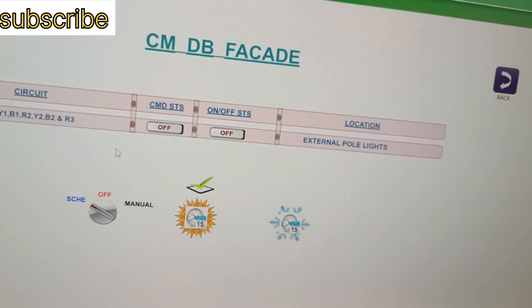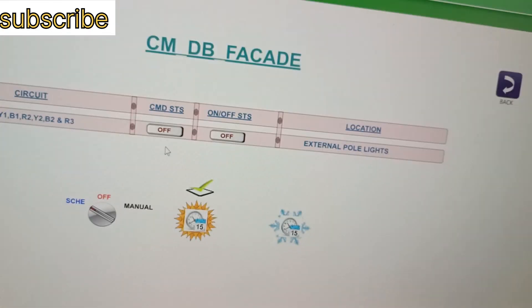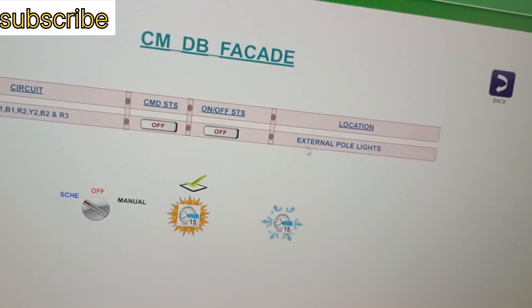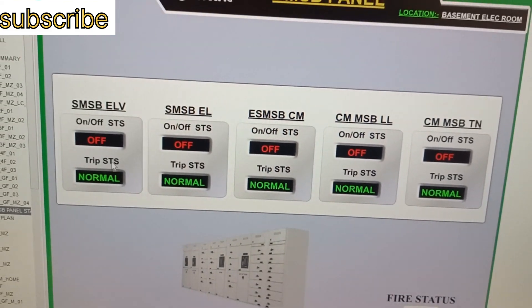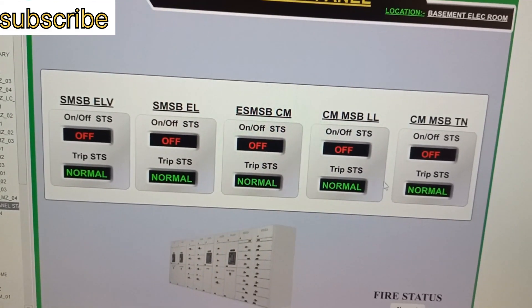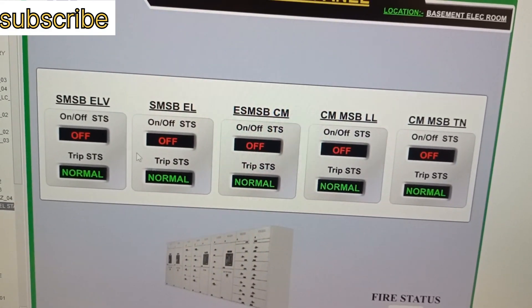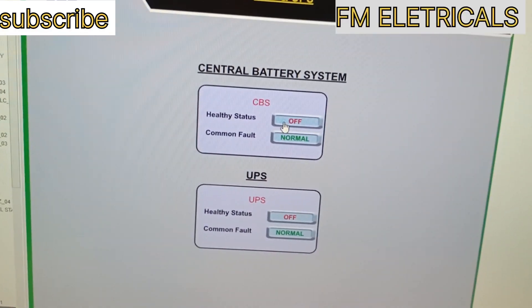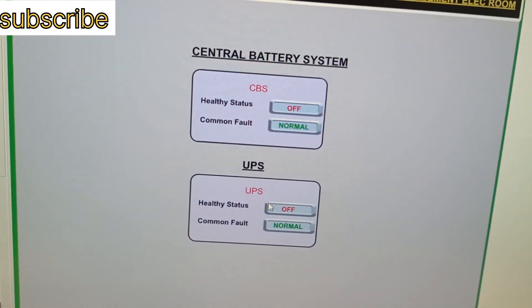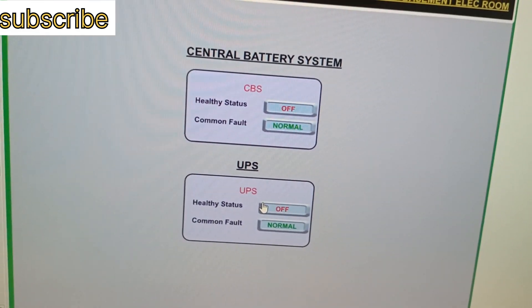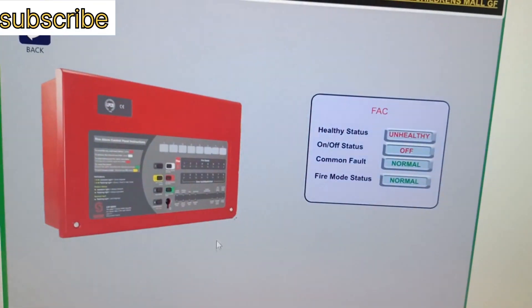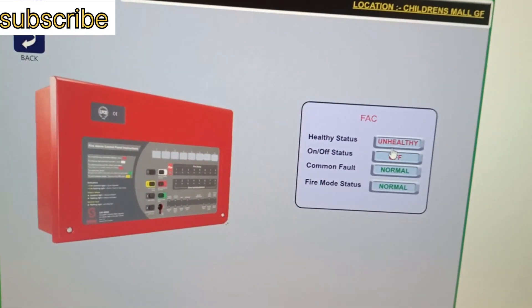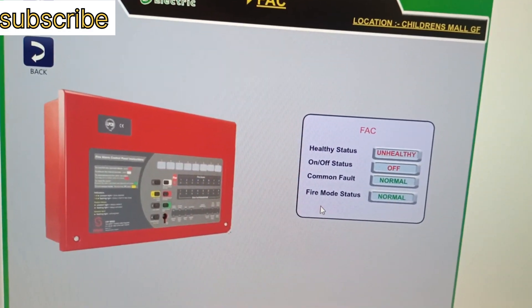For facade lights, these are the circuit numbers and we can get the on/off status and location from here. The SMSB status is showing normal. CBS is going to be connected to this existing system. UPS has already been reconnected to the new system. The FSCP is showing an unhealthy status, so we need to check this one.